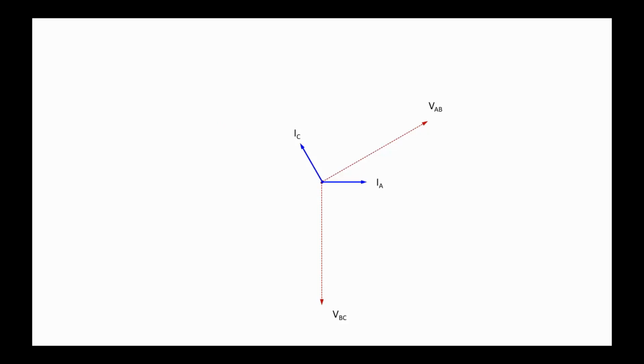Now, since the 2-element wattmeter only uses 2 voltages and only 2 currents, in this slide I've eliminated the voltage and the current that I'm not using in the 2-element meter. And I'm recognizing what we said in the earlier slide, that the element 2 voltage is no longer B to C, which is the more intuitive way of expressing the phase-to-phase voltage. We usually talk about A to B, B to C, and C to A. But the wattmeter is now looking for the voltage of the C phase. Remember, element 2 is connected to the C phase as hot, and the low side is now the B phase. So what we're looking at isn't VB to C, it's VC to B, which is why I invert the vector.